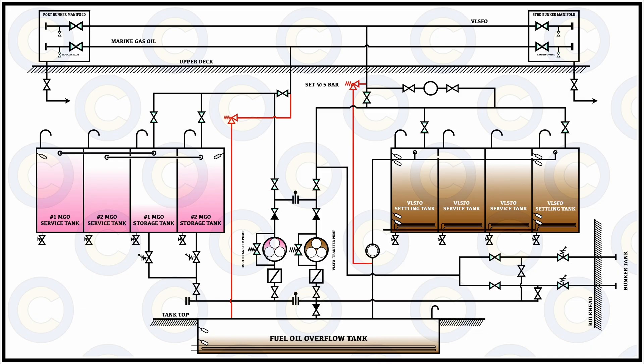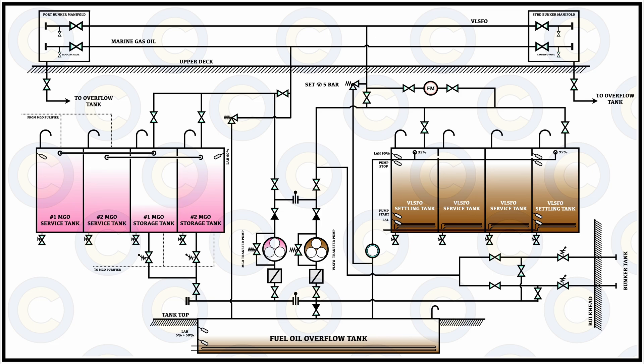That is why before every bunker it is very important to keep the overflow tank in an empty state and make sure that the alarms, that is the floats for the overflow tank, are tested. Also for the bunker tanks it is very important to test the alarms prior to taking bunker into the dedicated tank to make sure that in case of an emergency the bunker tank would be giving the correct indication, and also you will get an instantaneous alarm if there is a chance of rapid filling or any mishap to happen which can lead to an overflow or a spill.